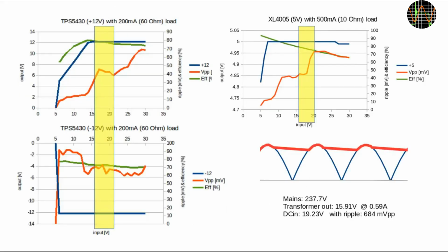Based on the measured performance graphs of the DC to DC converters, which I repeat here, we can see the expected performance depending on the DC input voltage range from the rectifier, which I indicate with the yellow band here. It's a band and not a line because the voltage will vary based on fluctuations of the mains voltage, which in the UK is normally 230 volts minus 6 plus 10%, so 216 to 253 volts.